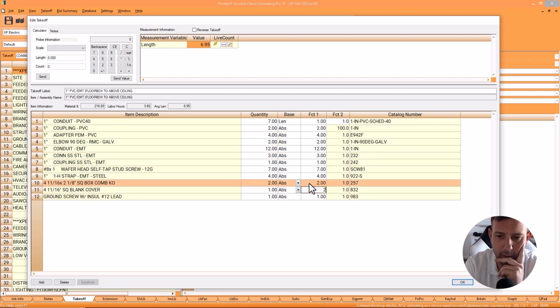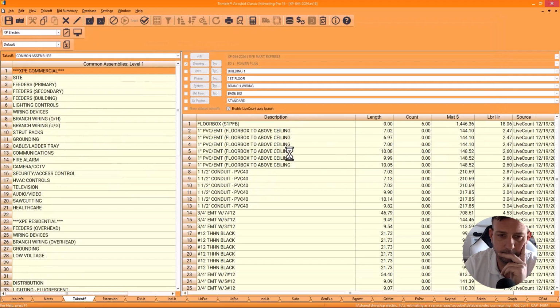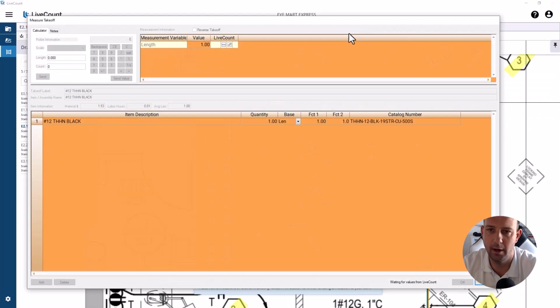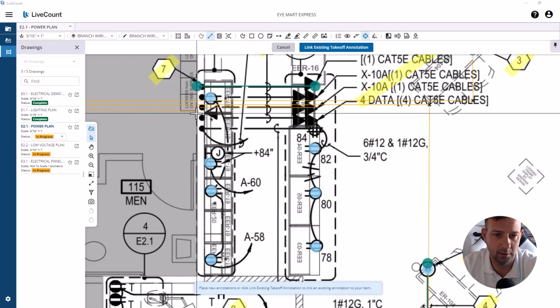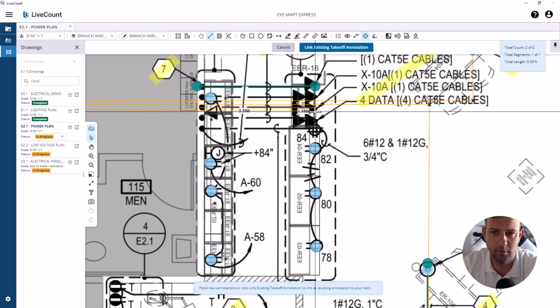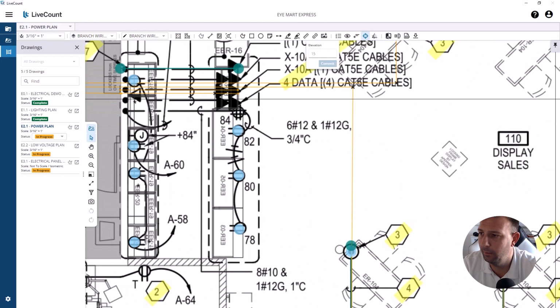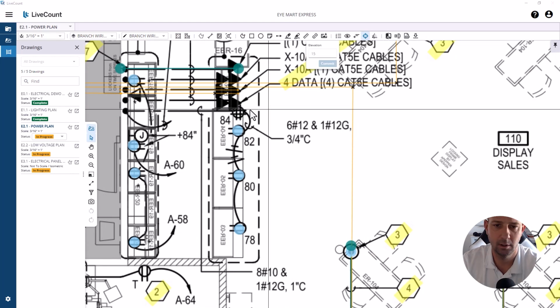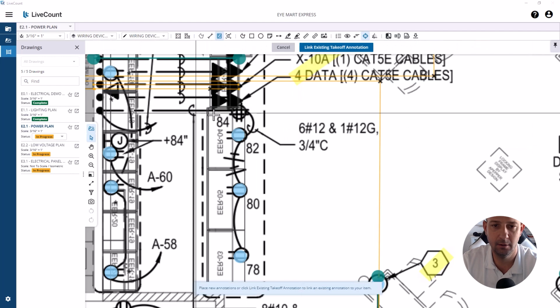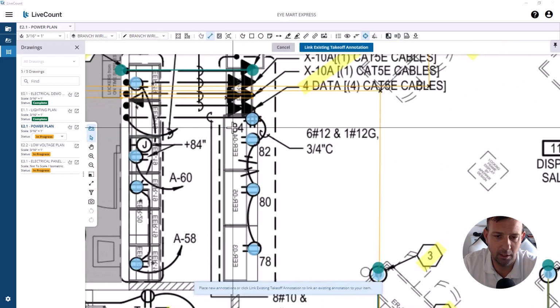Let's call that 2 boxes. Nice. Now let's grab the wire. Now that we've got conduit infrastructure, call this 15. As far as under the counter stuff, we probably would wire that in flex, but I'm just going to use EMT for now. So branch wiring, EMT 8480.